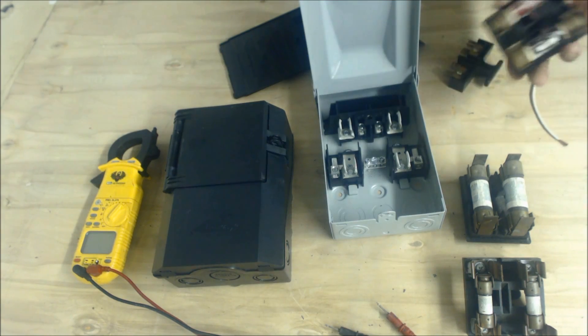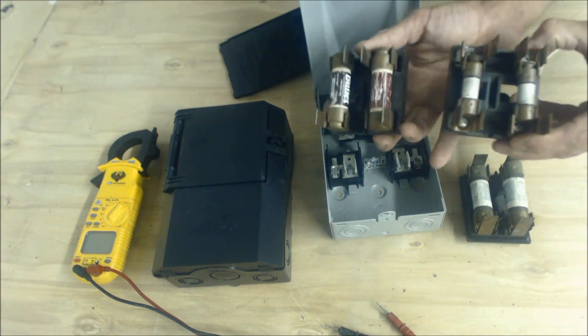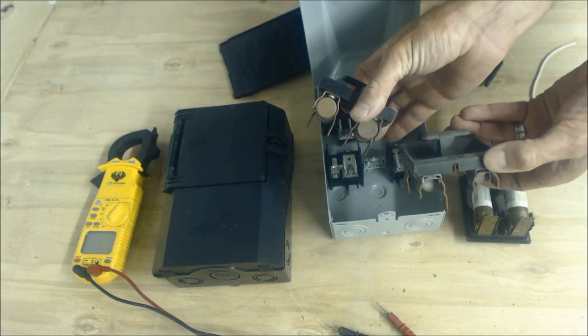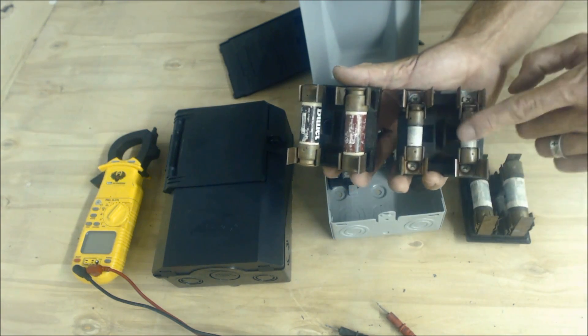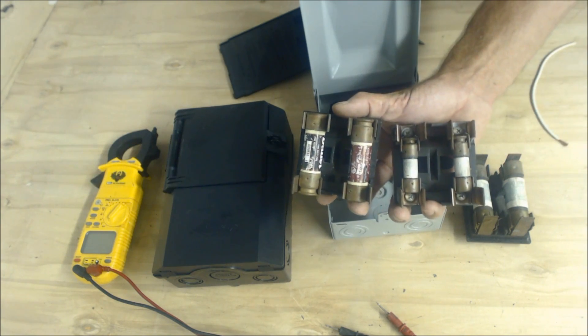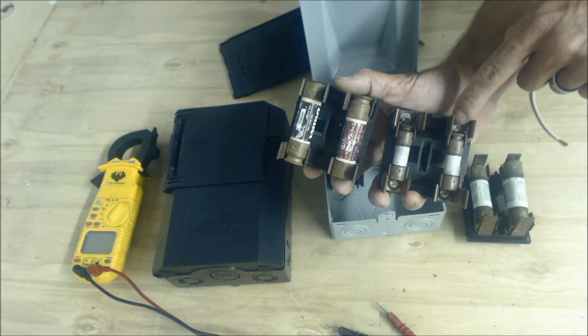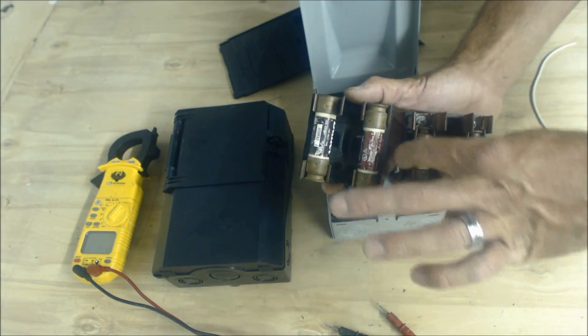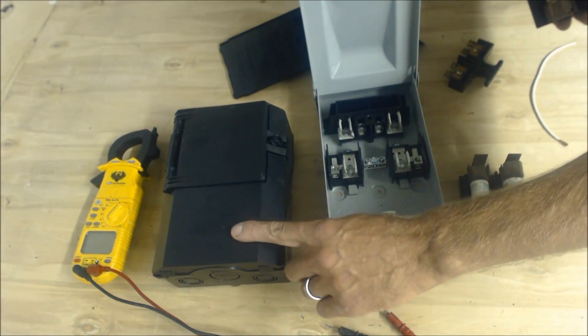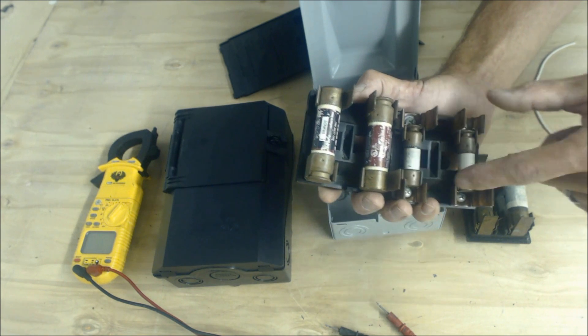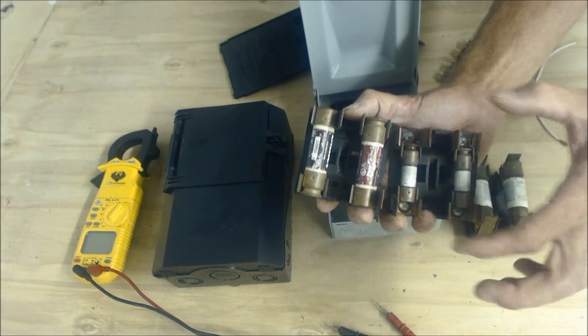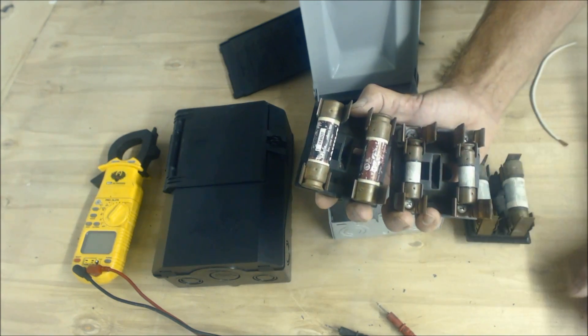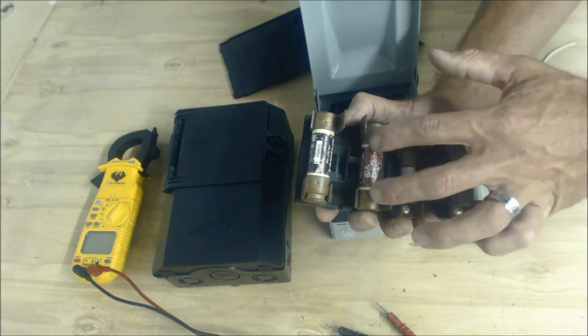You have a couple different fusible disconnect handles right here. The fuse holders, so these are 30 amp fuse holders, and these are 60 amp fuse holders. Really, the only difference is they take out these, the, this portion right here, at least on the Midwest version right here, they just take out these portions right here, and then you're left with these, which are the same as this, and then it will hold the 60 amp.